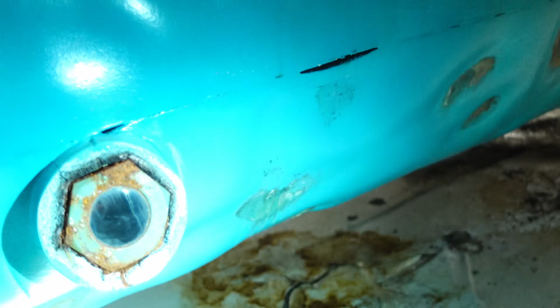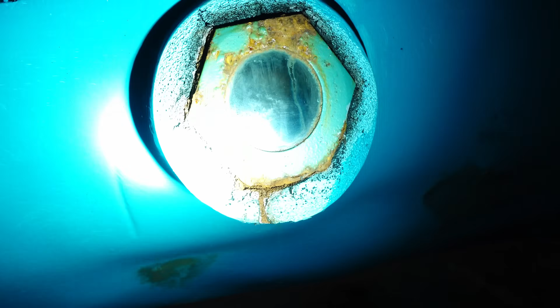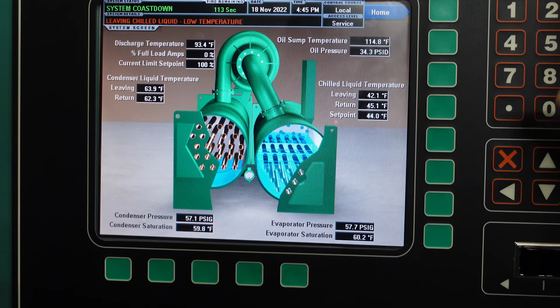Oil pressure's maintaining. We're only doing 31 hertz. It's perfect. We can look in here, see if we got anything. Oh yeah, we are bubbling. So you can see the refrigerant, got plenty of activity in there. That's good. All right, honestly, we were looking just fine. We just cycled on set point. We did have to make some calibration adjustments.